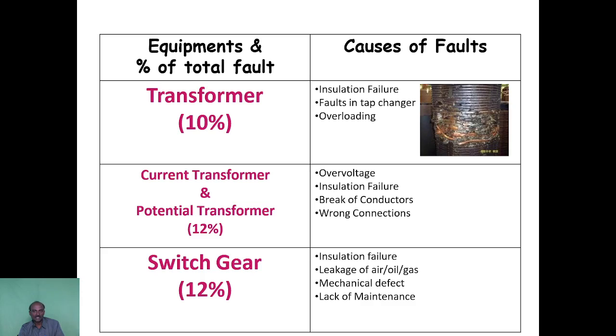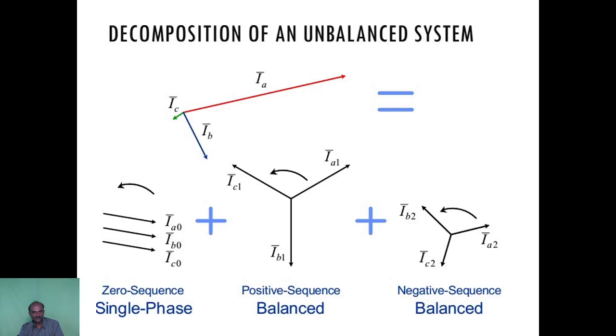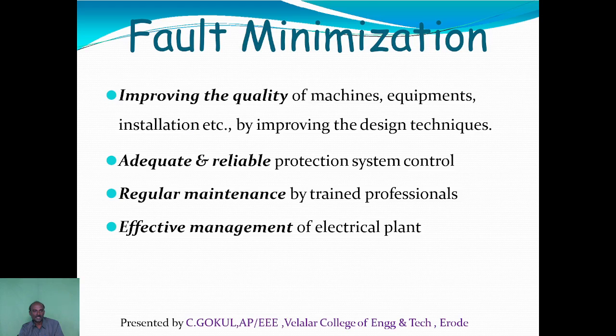Transformer faults are due to insulation failure, faults in tap changer or overheating. Current transformers and potential transformers are affected by over voltage, insulation failure, break of conductors and wrong connections. Non connections is also causing fault. Symmetrical components are used to analyze the unbalanced system.